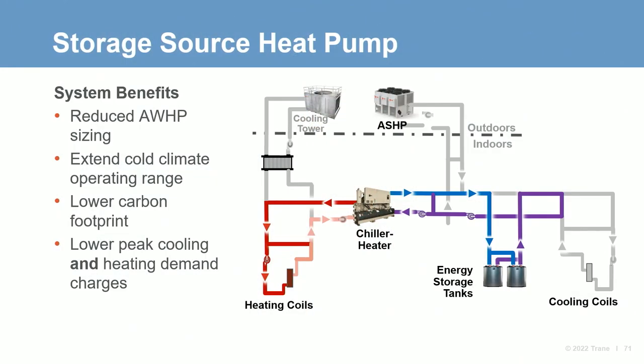The base system that Charlie and Dan introduced is reliable and will serve many applications well. However, specific building load profiles may be better served by other chiller heater configurations, like the dedicated air-cooled chiller system that Dan described earlier. McCracken introduced a new thermal energy storage system in the July 2020 issue of the ASHRAE Journal that can take advantage of the non-coincident heating and cooling loads. The new storage source heat pump system can balance building loads and enable the capture and storage of yesterday's waste energy for tomorrow's heating.